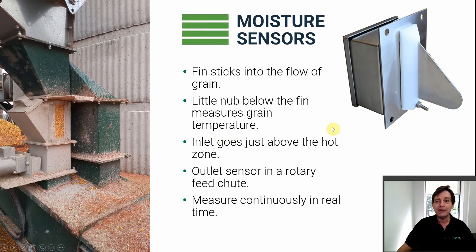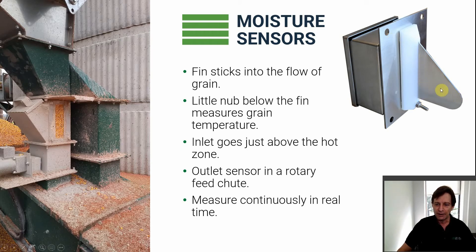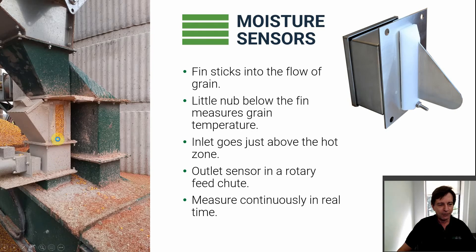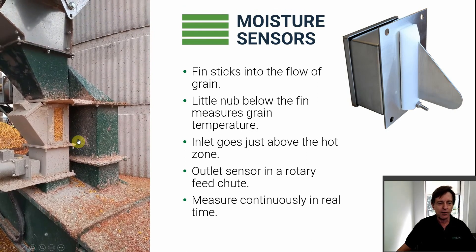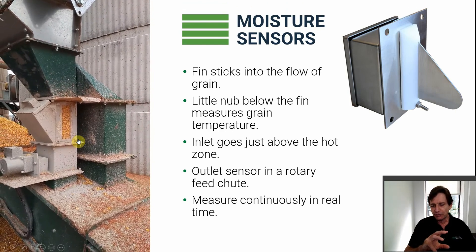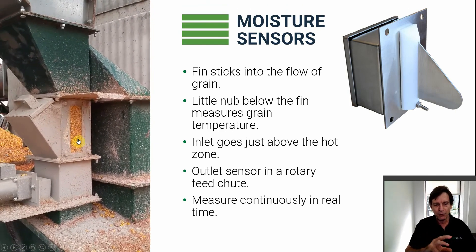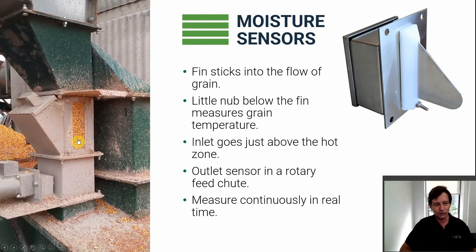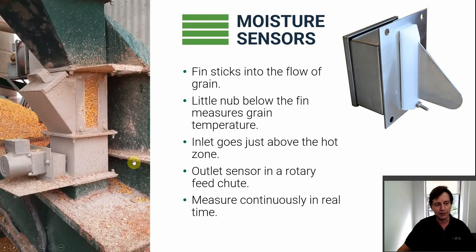One of the key things with Dryer Master is the moisture sensors — there are two, one at the inlet and one at the outlet. This is the moisture sensor; it's a fin type. The fin sticks into the flow of grain to measure moisture, and a little nub at the bottom measures grain temperature. At the outlet we put it into one of our rotary feed chutes. There are bypass versions and inline versions. About 40 to 50 bushels an hour goes through the chute; the rest goes over the side.